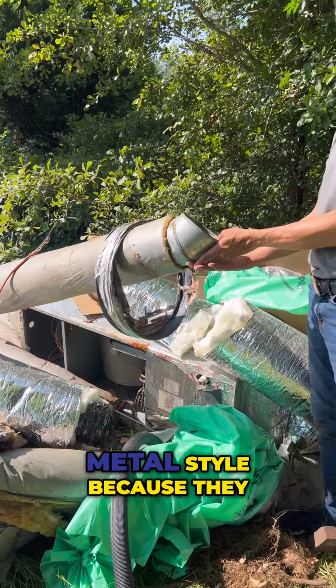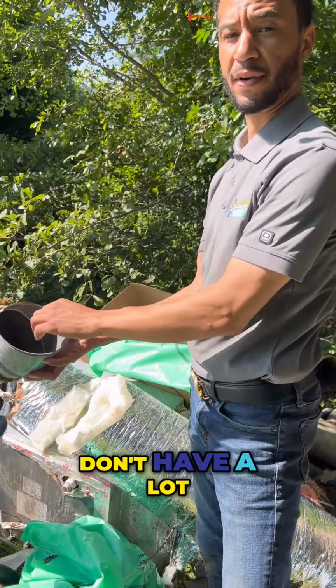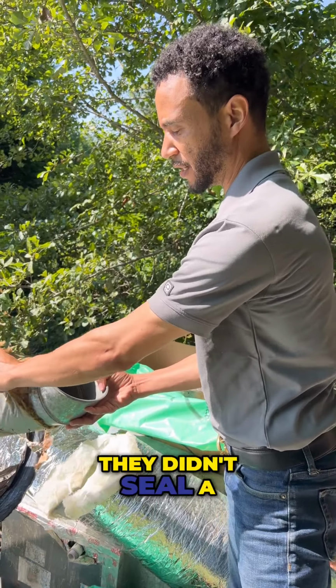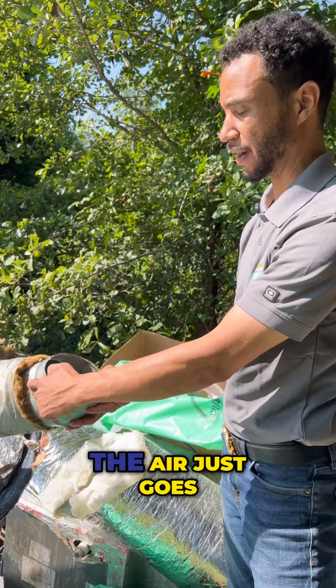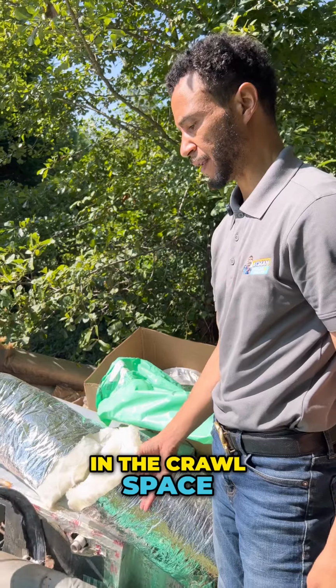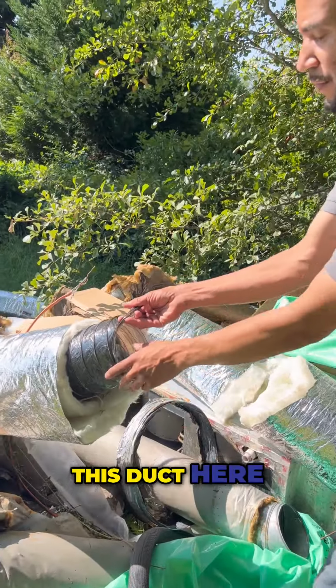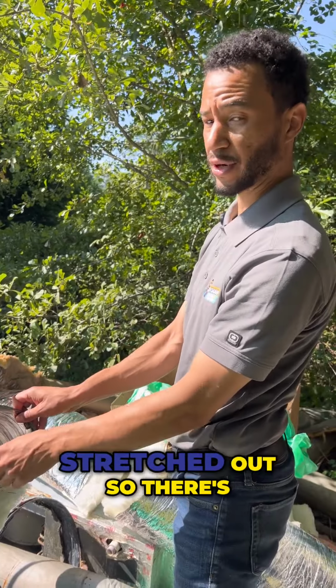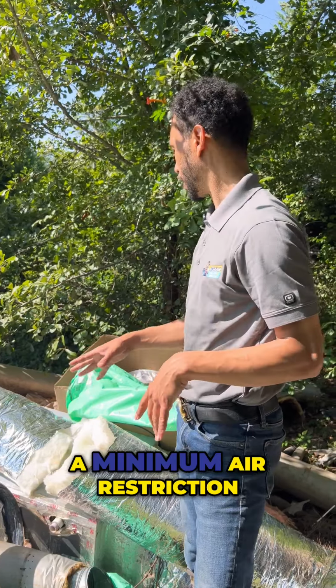Now, I like the old metal style because they don't have a lot of air friction. Unfortunately, they didn't seal a lot of these back in the day, so a lot of the air just goes into the crawl space. We replaced it with this duct here, and made sure it's nice and stretched out so there's minimum air restriction.